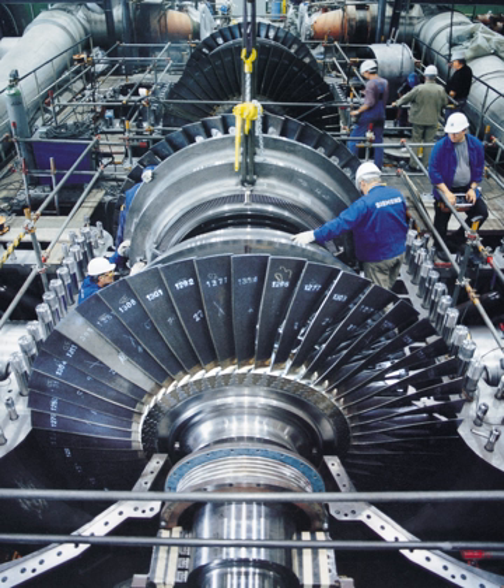However, it is not the only challenge. In addition to the power used by a load to do useful work, termed real power, many alternating current devices also use an additional amount of power because they cause the alternating voltage and alternating current to become slightly out of sync, termed reactive power. The reactive power, like the real power, must balance, that is, the reactive power produced on a system must equal the reactive power consumed, and can be supplied from the generators. However, it is often more economical to supply such power from capacitors. See capacitors and reactors below for more details.